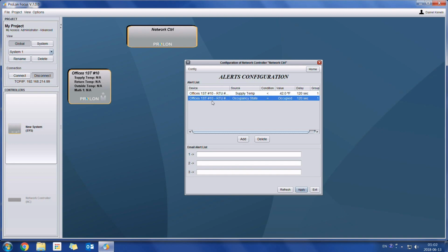We can put up to 100 lines here. So we could technically have up to 100 separate email alerts, or if we start grouping them together, then we would not be able to reach that 100 limit. So it really depends how many controllers and how many points we are trying to monitor and be alerted. So we can put up to 100 lines in this alert configuration page.